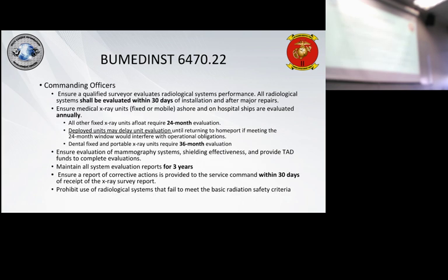Commanding Officers ensure a qualified surveyor evaluates radiological systems performance. All radiological systems shall be evaluated within 30 days of installation and after major repairs, so 30 days. Ensure medical x-ray units, fixed or mobile, ashore and hospital ships are evaluated annually. It's going to ask you how often: annual. All other fixed x-ray units afloat require 24-month evaluation, and deployed units may delay the evaluation until they get to their home port within the 24-month window. Maintain all system evaluation reports for 3 years.